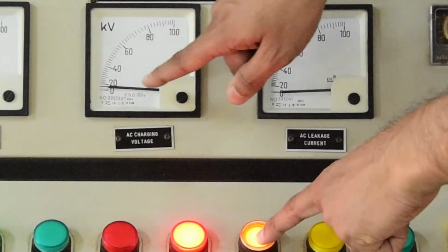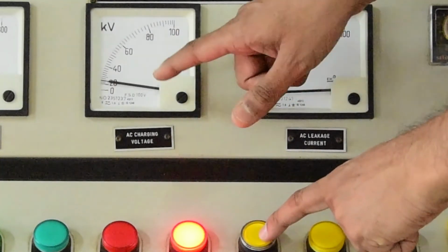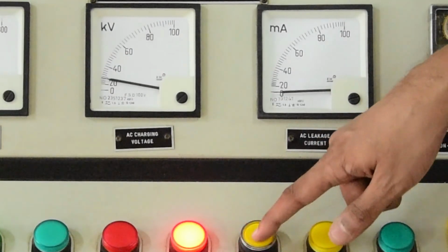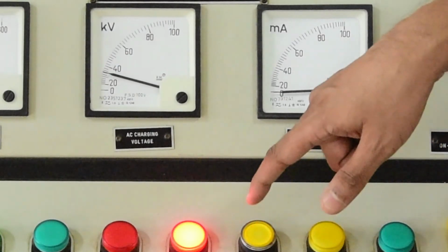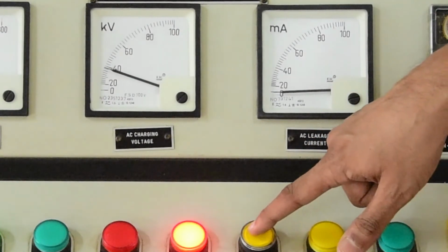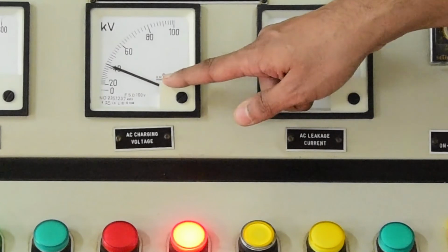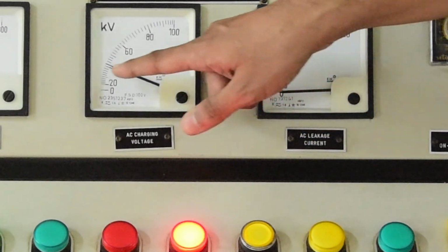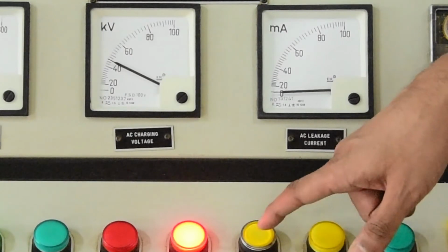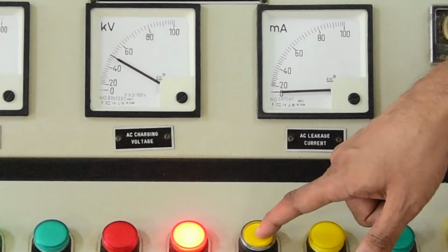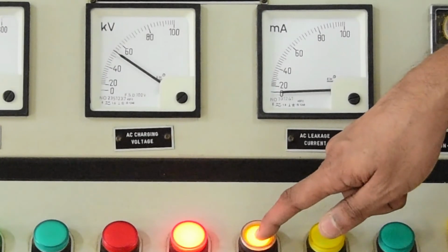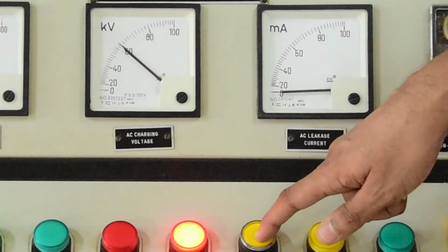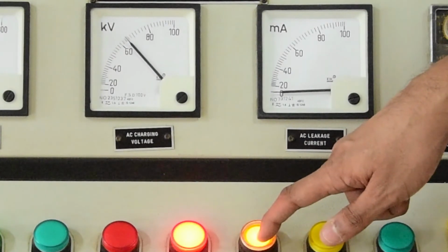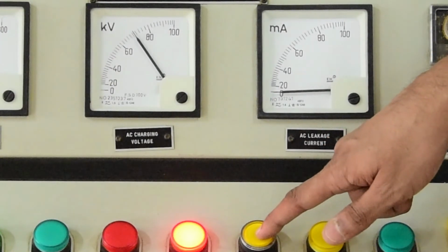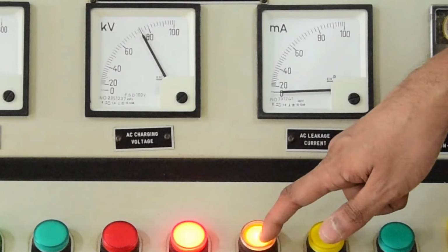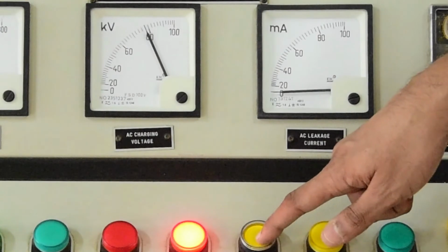While I am increasing this, you have to focus your attention on the dial. You can see that the voltage is increasing. We have to increase it gradually. Instead of pressing continuously, we press in short intervals. You can see here the voltage has now reached a potential of 40 kV. Again we are increasing. Spacing is set to 10 millimeter. We increase further, and now it is reaching 70 kV. Further I am increasing to reach 80 kV.